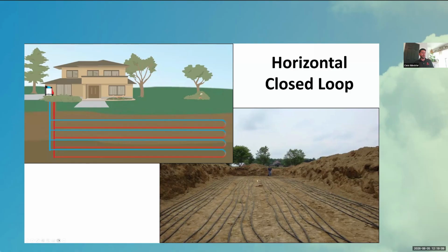This involves digging down a certain depth below the frost line. At this house, it was somewhere between 5 or 6 feet, but we have other systems up north where we go 10 to 12 feet deep. We dig a pit sized based on the energy we're going to take out to heat that house. This ended up being a 3-ton system, with 4 separate loop systems here, since in the Northeast we typically do 3 plus 1 for tonnage, and those loops are approximately 800 feet each.